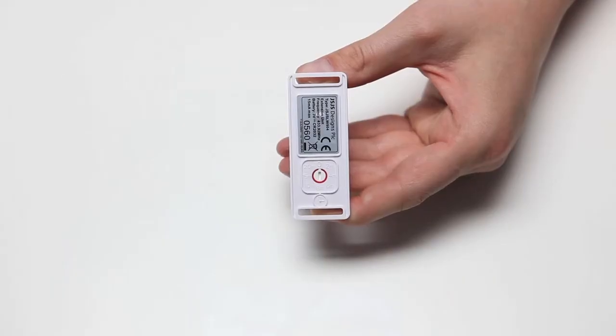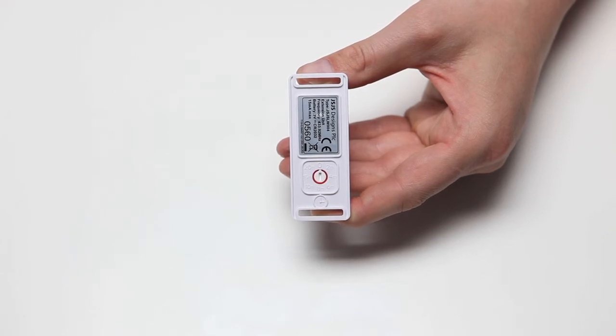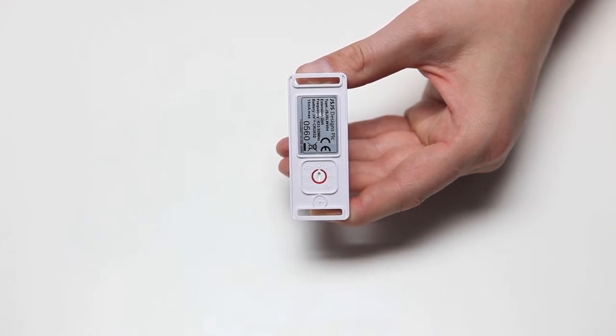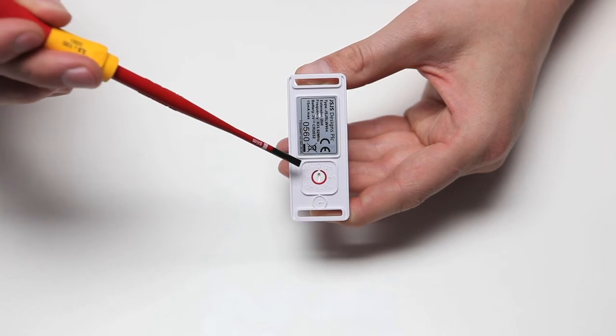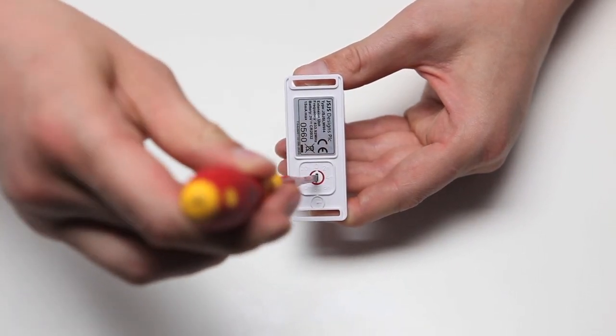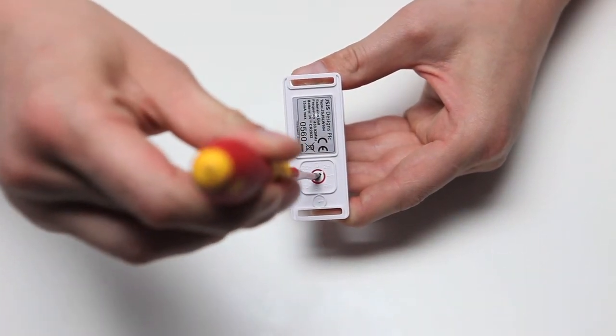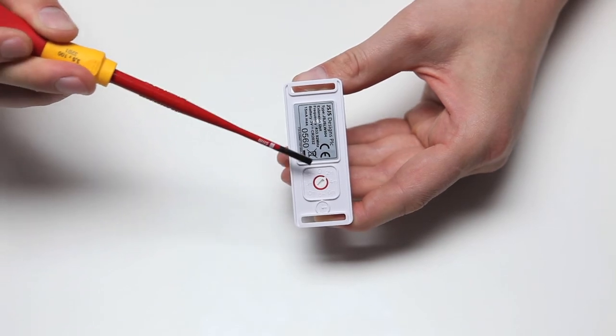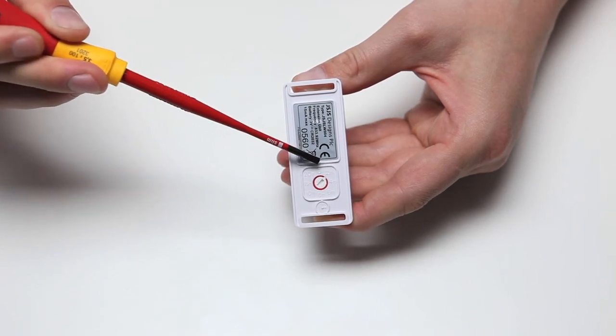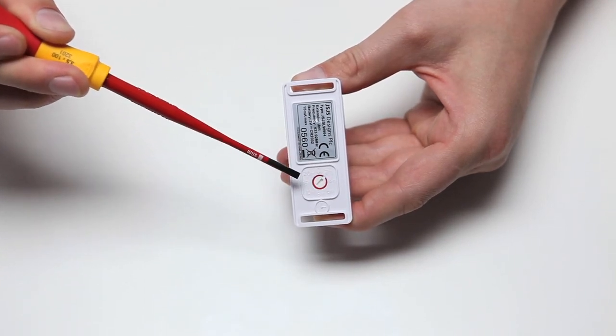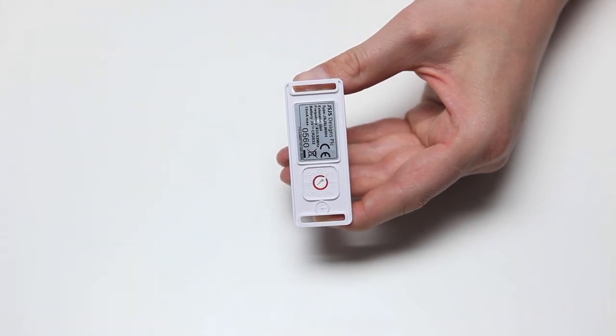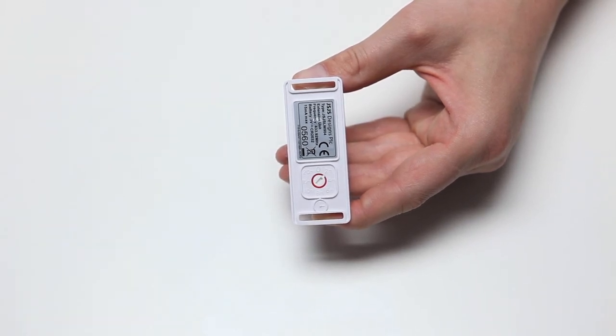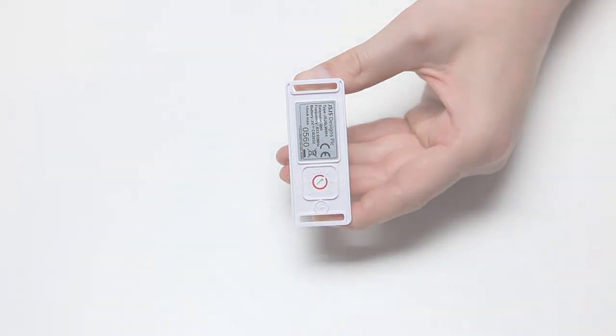To set the magnetic switch up to transmit an off command after a set delay, move the delay switch on the rear of the electronic section using a small flat head screwdriver. It is possible to set a delay period from 0 to 20 minutes from the moment the switch is tripped until the off command is sent to turn linked devices off.